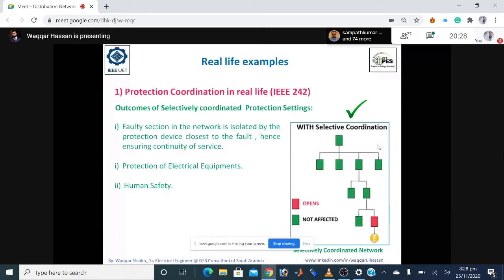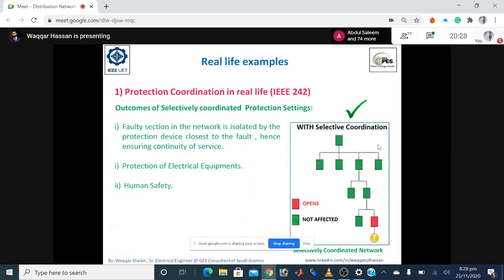You can see this scenario. If any fault occurs in your mobile charger, as you can see here, the yellow colored fault symbol, it will only affect the nearest breaker associated to that socket. That is the branch circuit breaker in your service entrance panel. So this fault will not propagate throughout the network to trip all the protection devices. You can see that all the protection devices are in green color. It means the fault has only affected the nearest circuit breaker in the electrical architecture.